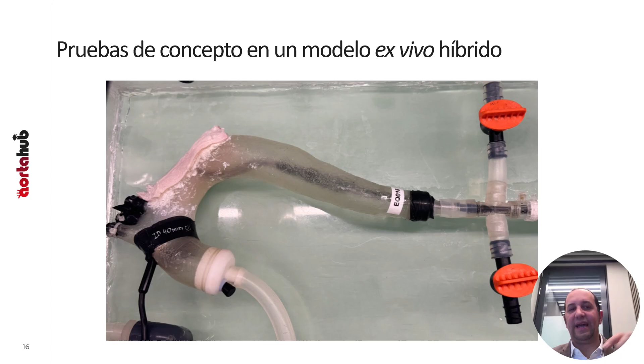We invented various experimental systems to test our prototypes. I'll show you a couple today. The first one is what we refer to as ex vivo hybrid. In this process, we create a full-scale 3D graft using soft resin and replace the implantation site with animal tissue, the graft coils in this case. We connect a piston pump that drives flow from the ascending aorta like a heart, and we can use anything from water to blood or high viscosity fluids depending on what we want to test. We capture footage through a port installed at ground zero using an endoscope, but if the fluid isn't clear, visibility is poor. I'll show you a few examples later on.